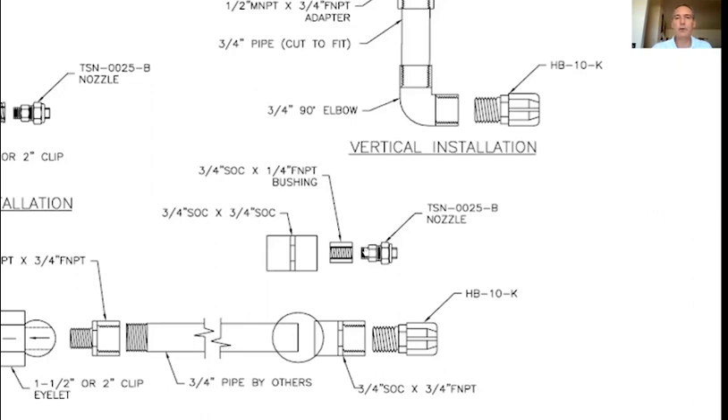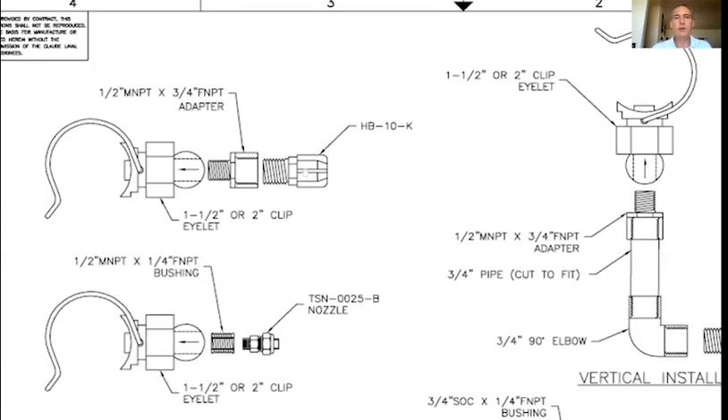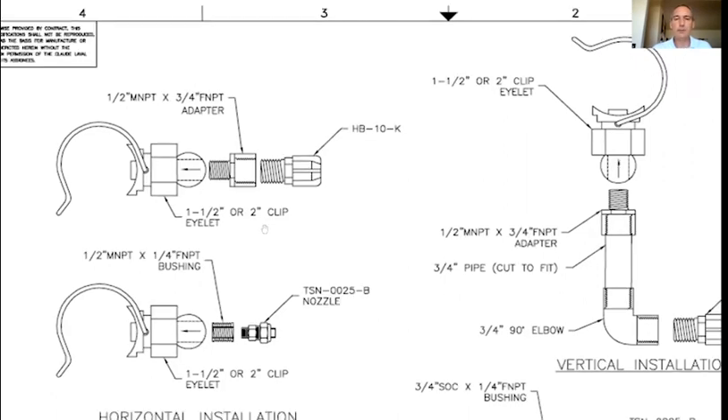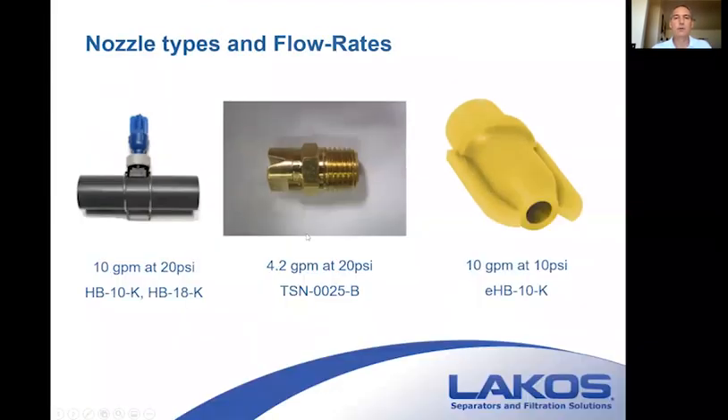The same applies to the quarter-inch spray nozzles — they're quarter-inch, so they need to be reduced to fit into a three-quarter-inch adapter to work with three-quarter-inch pipe. The same applies to vertical-down installations in depressed areas of the basins. You can install the clip on the bottom of the pipe and let it extend down, keeping piping above the depressed area so you're not cluttering down below. The quarter-inch nozzle without the adapter will not thread into the clip — it's a different size threaded fitting.